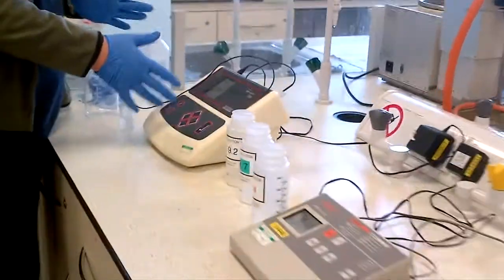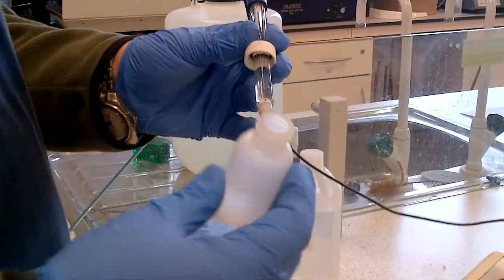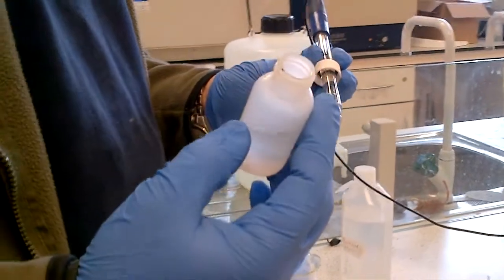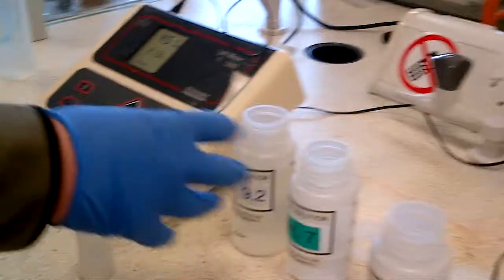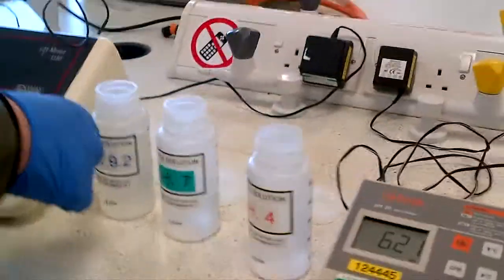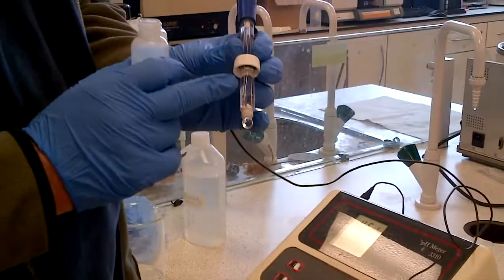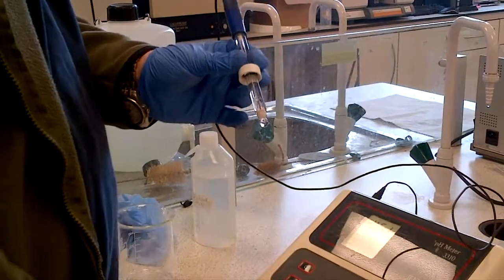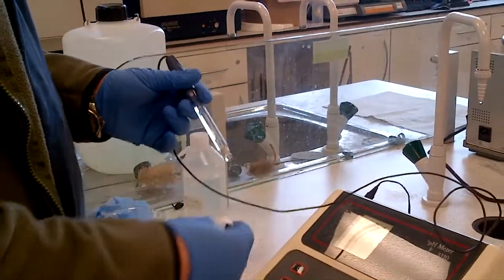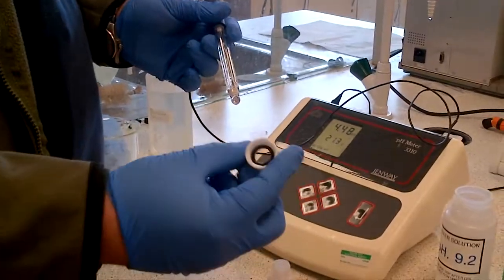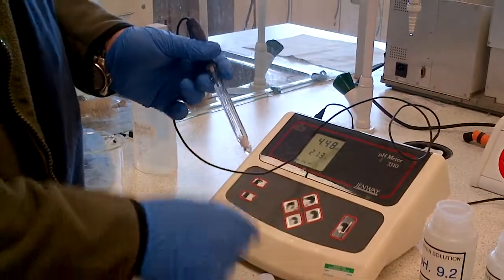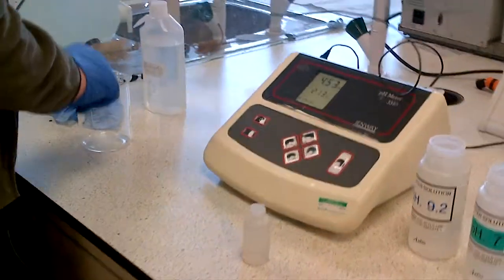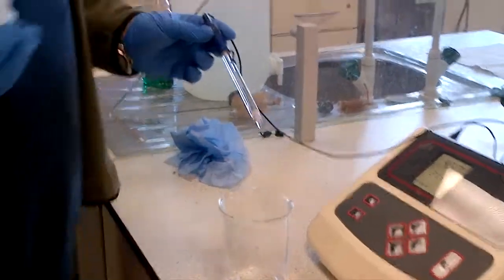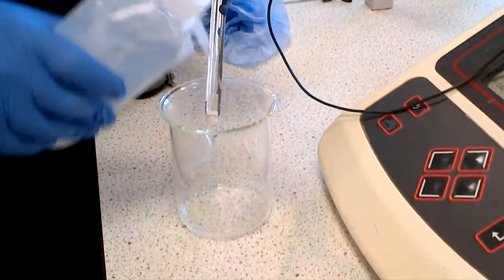So let's show you how to use the Jenway meter. The electrode, first and foremost, is kept in a reservoir of buffer. If that runs dry, when you're doing a pH calibration measurement you can take one of the three buffer solutions and top this up. You don't want that to be dry, because you want to protect the integrity of the electrode. Likewise, when you're measuring pH, you can take off the jacket and seal neck while using this, so it's free from contamination. So let's take the electrode, and the first thing we need to do is wash the electrode.